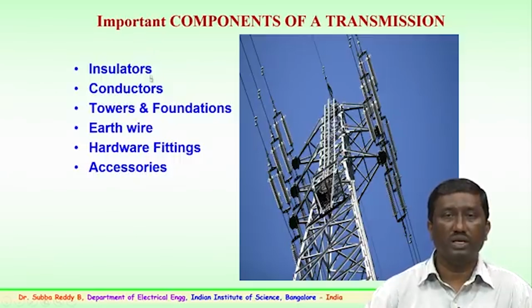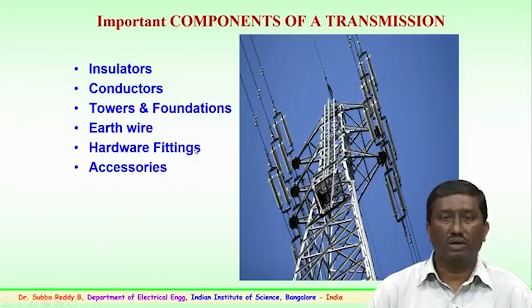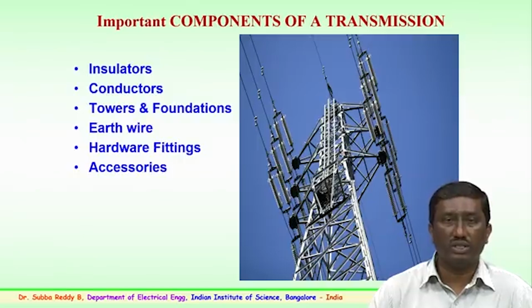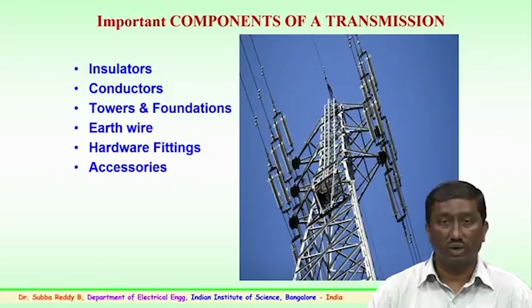Then we have the hardware fittings. Hardware fittings consist of various types. Hardware fittings are used to connect insulators to the tower. So, these are the yoke plates, end yoke plates which are being connected. Apart from yoke plates, we have corona control rings. Then we have several other components which are used for stringing the insulators to the tower. We will be looking into the hardware fittings, the developmental aspects they have undergone over a period of time, and how the hardware fittings change when it comes to the 765 kV, 800 kV voltage levels, that is, the UHV voltage levels.